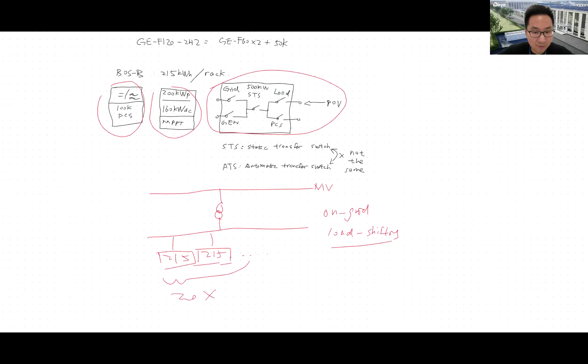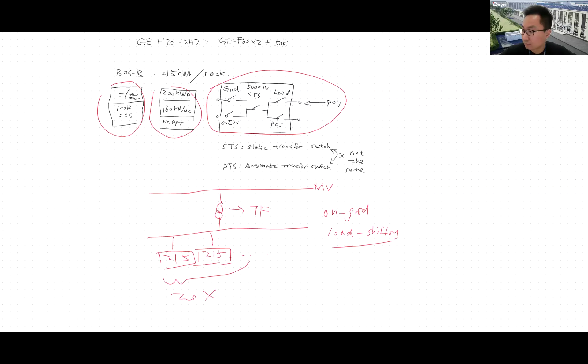What you will do is have the 215 AC coupled onto your low voltage bus. You can have up to 20 units working under one grid access point, that's the transformer, the grid access point. And you can have your load down here.